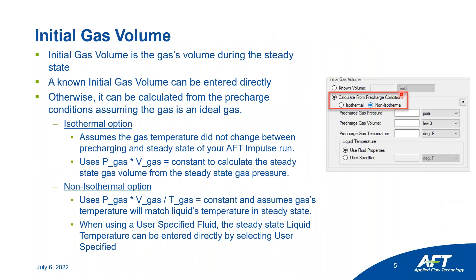I mentioned initial gas volume earlier as one of the required inputs. A known initial gas volume can be entered directly. But what do we do if we don't know the initial gas volume at steady state? We can click this 'calculate from pre-charge conditions' radio button instead and these options will drop down. From that we have two options: we can assume isothermal or we can do a non-isothermal calculation to get the initial gas volume at steady state.